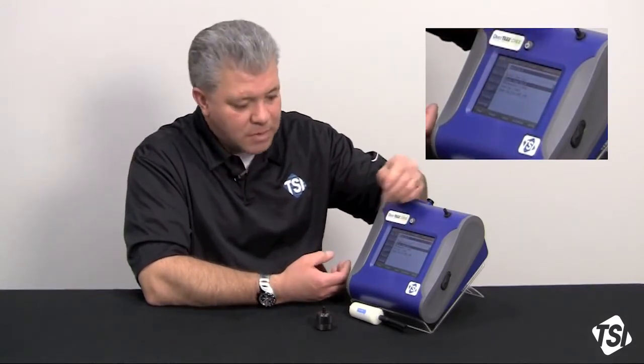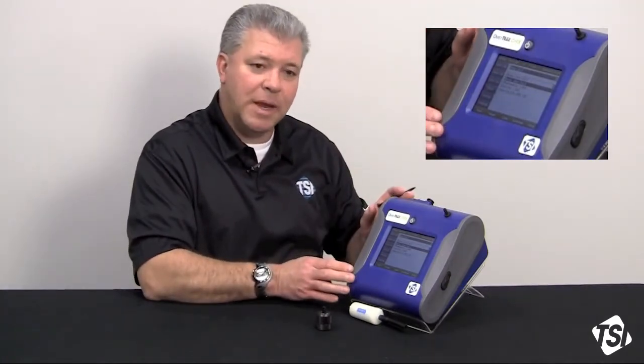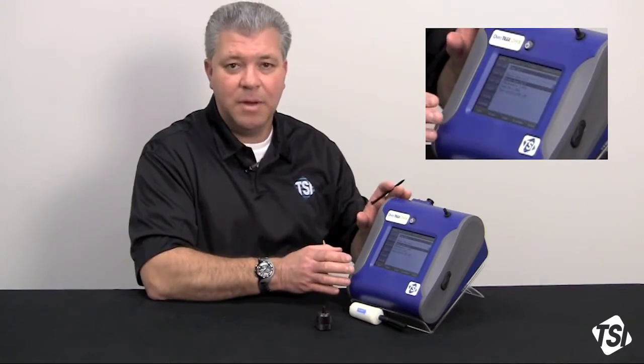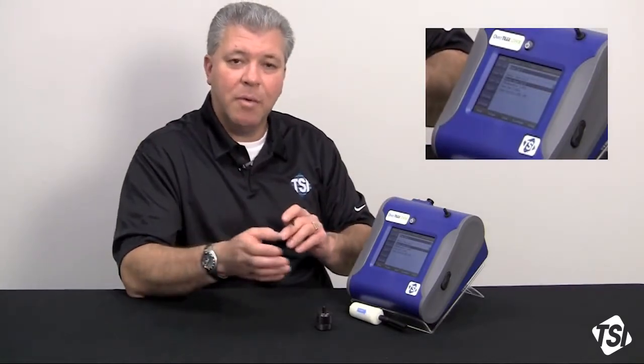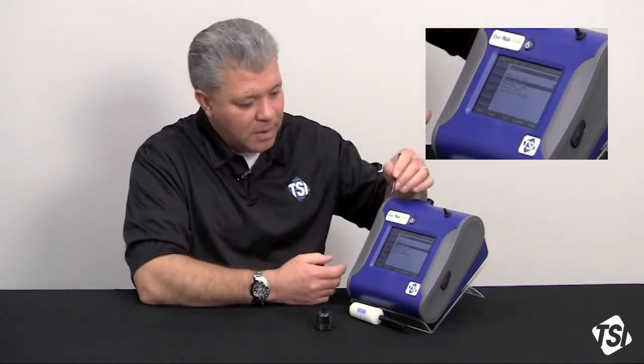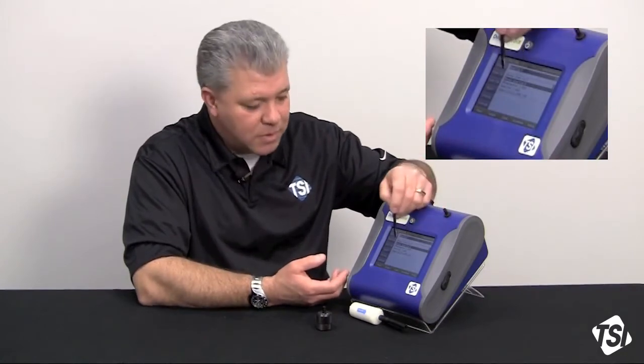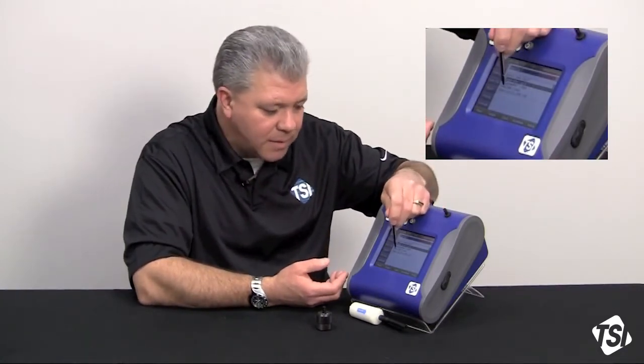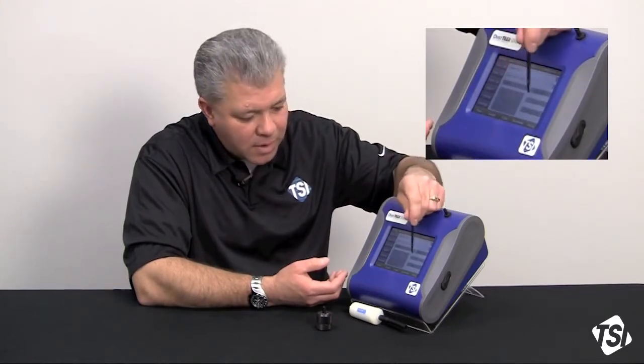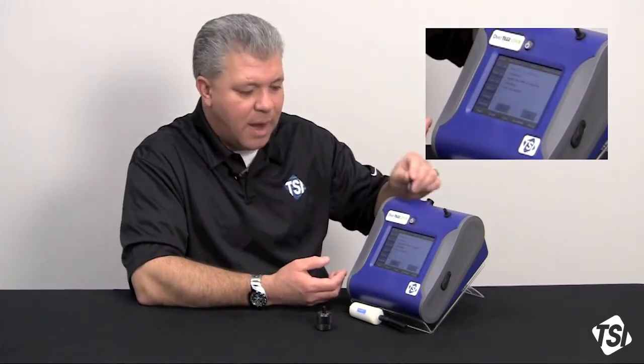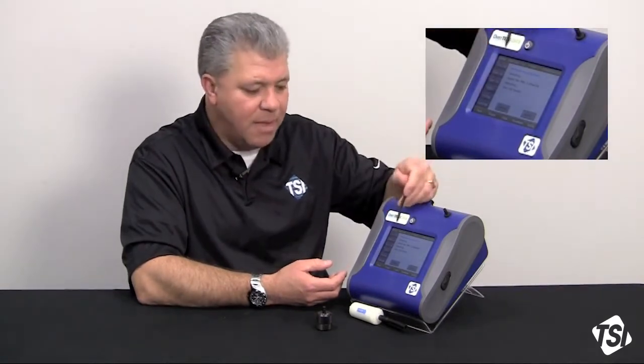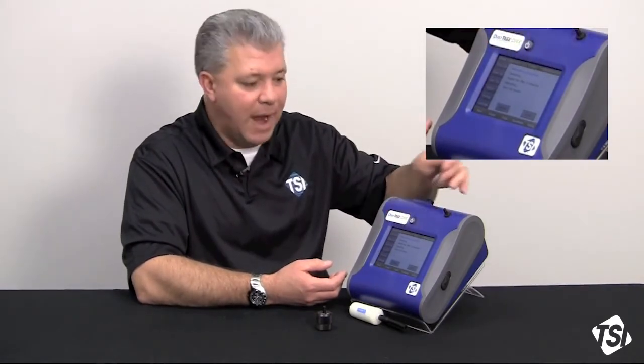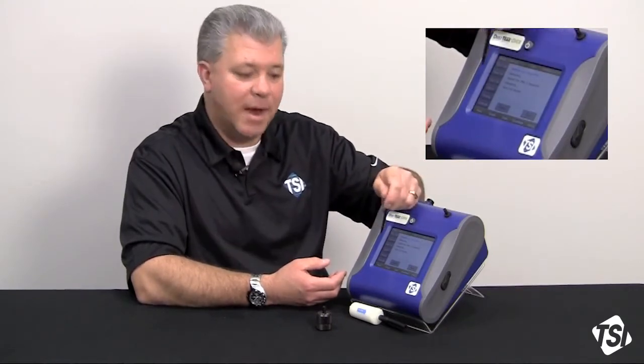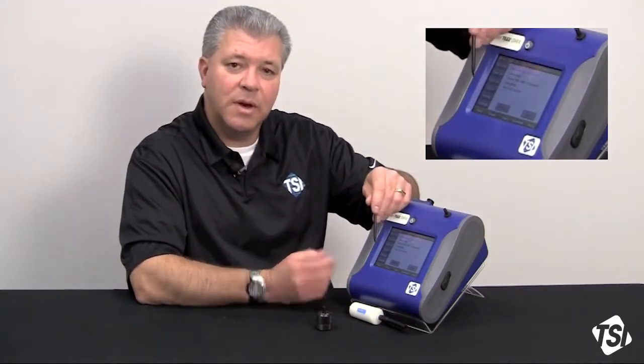It's 1.0. So I want to do a real-time size correction factor. The reason for being able to do that is you don't have to take the time to do all the gravimetric sampling, which may take several hours to a couple of days to complete enough samples. Now, you can do this in real-time. So what we're going to do is select size correction factor, and we're going to come down here to custom calibration. A new window will pop up, and on that window it's going to say sampling without an impactor, sampling with an impactor, and then at the end of the procedure it will come up with a new correction factor.